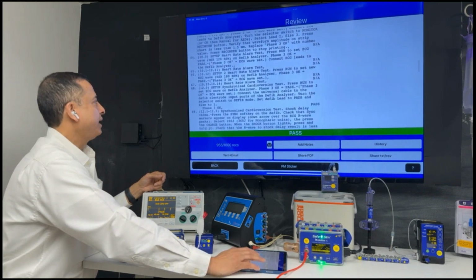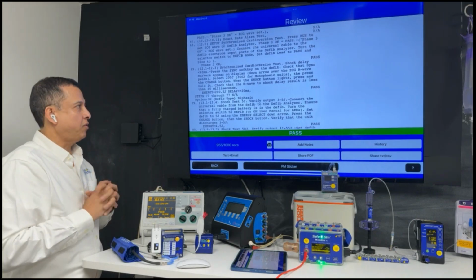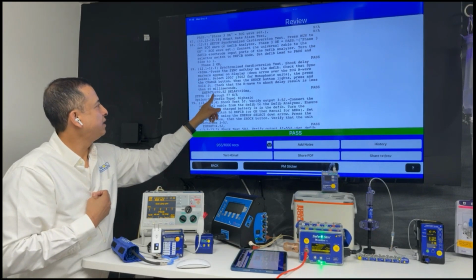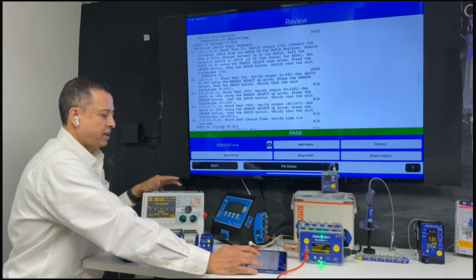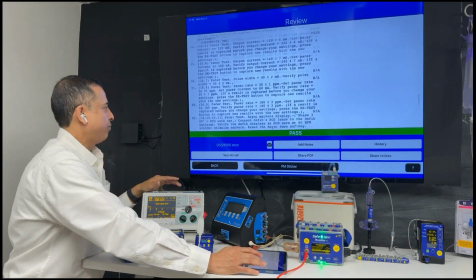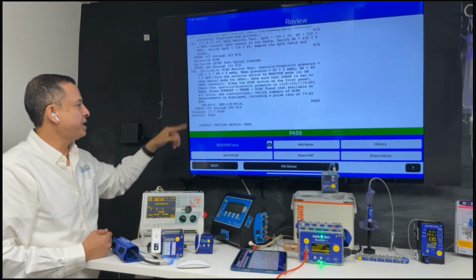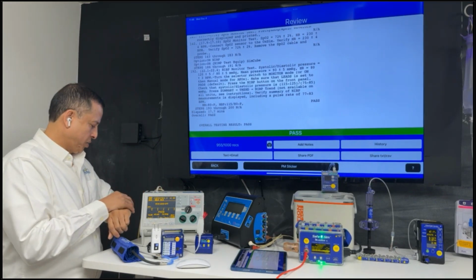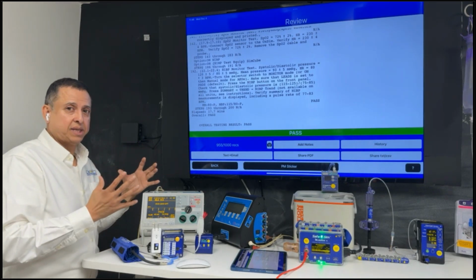So everything is all in here, and you have the ability to capture all this data in your report. So the results are next to the test. So here's the test, here's the result that passed. So we document it as kind of a procedure type report. And again, you have all of your tests, including your simulation tests, and I can take more pictures, add it into the report as I need to. So that's the different modes you can utilize the app in.